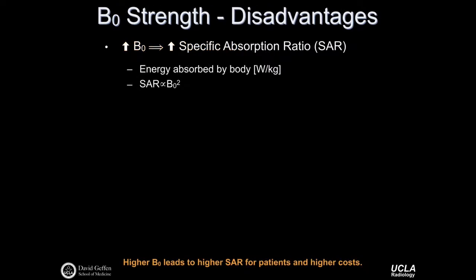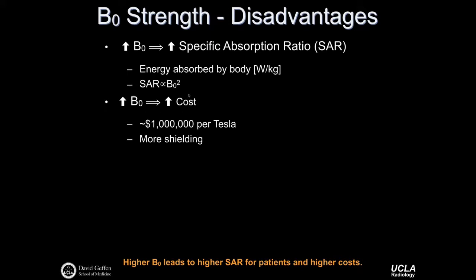Increasing B0 also has disadvantages. One is the associated increase in the specific absorption ratio (SAR), a number reflecting energy absorbed by the body measured in watts per kilogram. The deposition of RF energy needed to excite the spins contributes much more energy to heating the patient than to the excitation process itself. SAR is proportional to about B0 squared, leading to SAR limitations at higher field strengths. Increasing B0 also increases cost at about a million dollars per Tesla, requires more shielding, and makes siting high-field systems such as 7T quite costly.